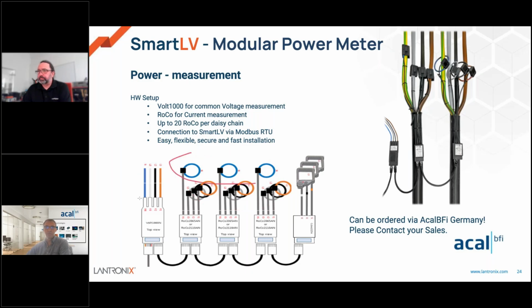To accomplish this, the volt 1000 meter samples the voltage and sends the samples to the current meters on the cascade bus. Each current meter uses these samples to calculate the power. The volt 1000 meter acts as a bridge between the Modbus master and the cascade bus. Only one cable needs to be connected to the RTU master, in this case to the SmartLV device, to measure up to 20 by 4, which means 80 power lines.